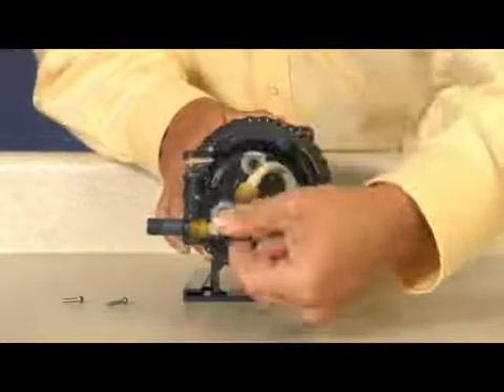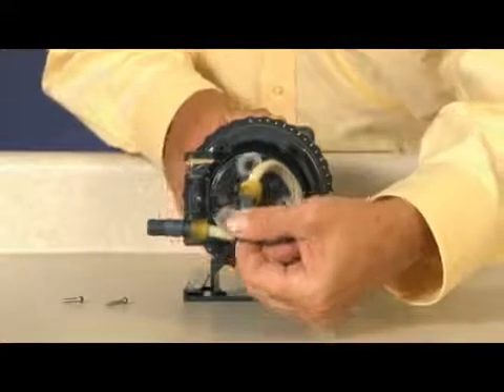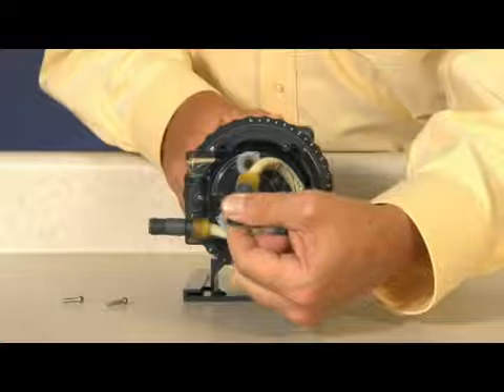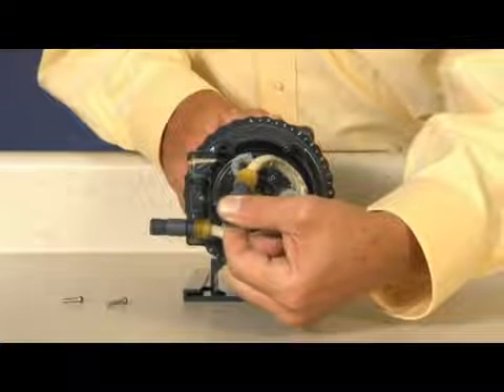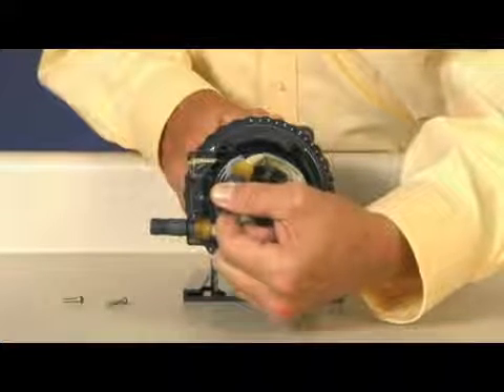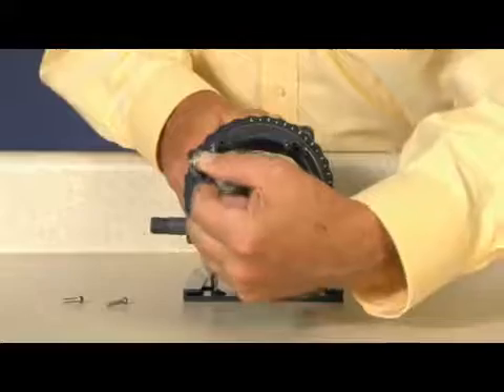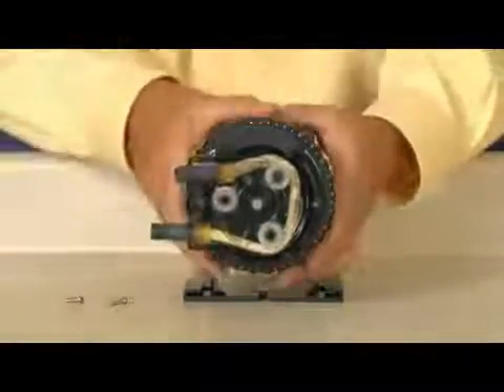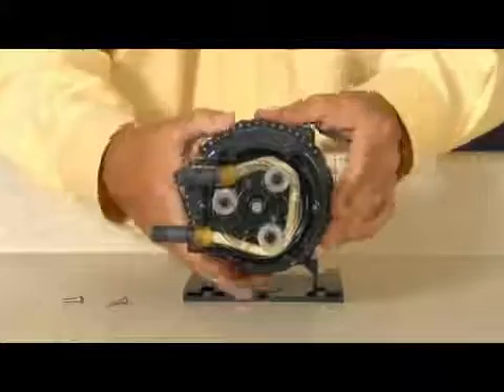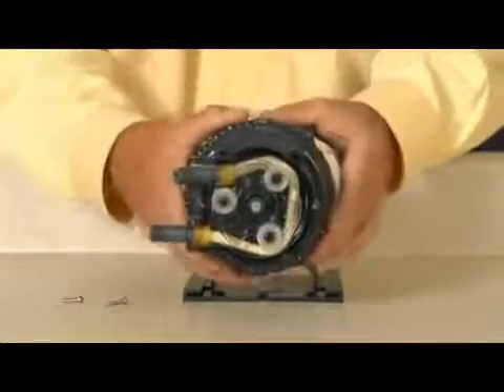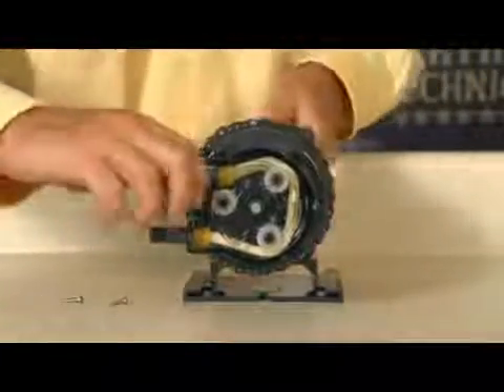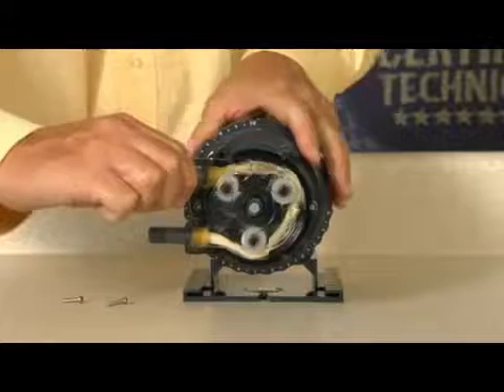Guide the tube with a slight tension toward the center to prevent pinching between the housing and roller assembly. If the tube is pinched during installation, discard it and start over with a new tube. When the tube reaches the discharge tube housing slot, turn the pump off. Turn the dial ring to setting 10. Hold the tube fitting firmly. Do not pull and turn the pump on.